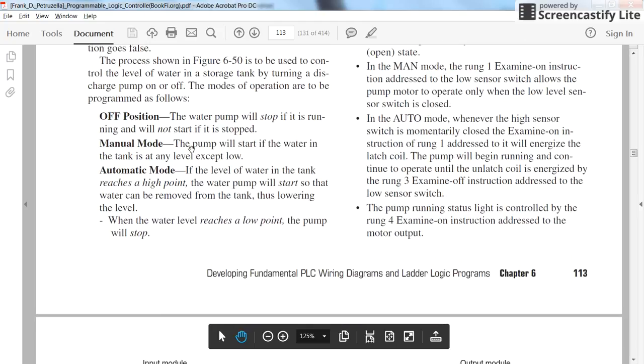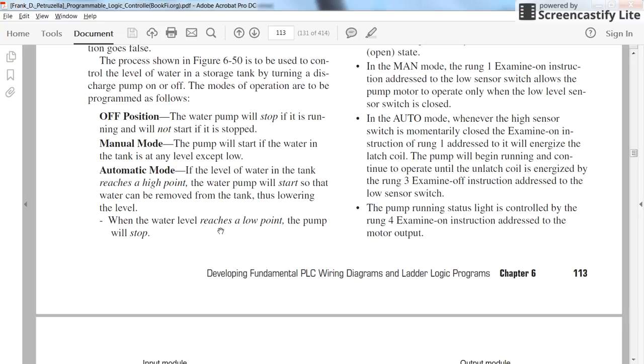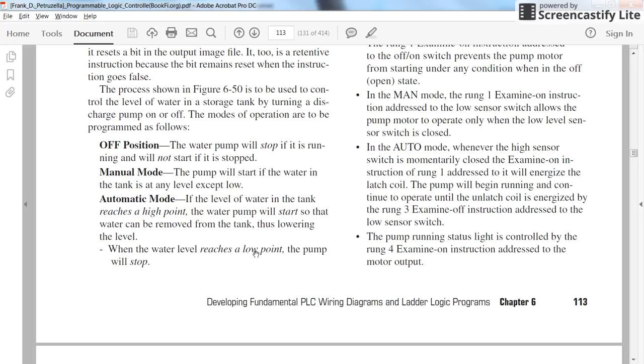Here is the explanation for the process. With the on/off switch in the off position, the pump will not be turned on. In manual mode, the pump will start if the water in the tank is at any level except low — so if the water level is above the low limit, the pump will be turned on. In automatic mode, if the water level reaches the high point, the pump will start to remove water from the tank. When the water level reaches the low point, the pump will stop.